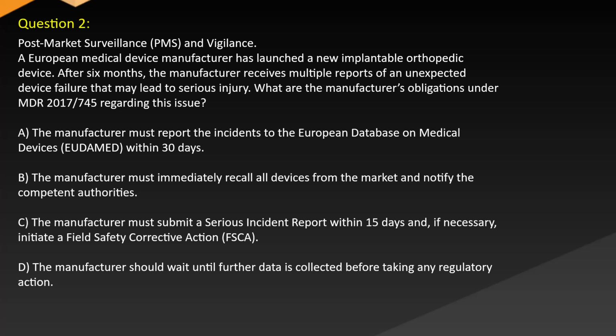The manufacturer must report the incidents to the European Database on Medical Devices (EUDAMED) within 30 days. B. The manufacturer must immediately recall all devices from the market and notify the competent authorities. C. The manufacturer must submit a serious incident report within 15 days and, if necessary, initiate a field safety corrective action (FSCA). D. The manufacturer should wait until further data is collected before taking any regulatory action.